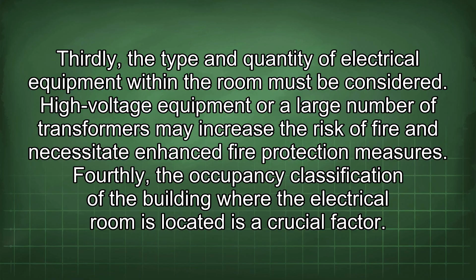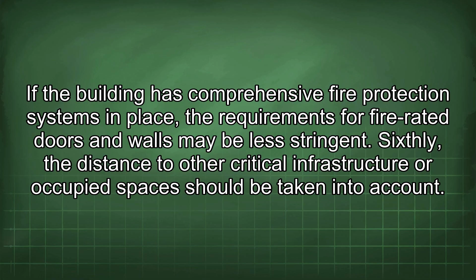Fifthly, the presence of other fire protection systems in the building, such as sprinklers and fire alarms, can influence the need for fire-rated doors and walls in the electrical room. If the building has comprehensive fire protection systems in place, the requirements for fire-rated doors and walls may be less stringent. Sixthly, the distance to other critical infrastructure or occupied spaces should be taken into account. Electrical rooms located close to critical infrastructure or occupied areas may require additional fire protection measures to prevent fire from spreading and causing damage or injury.